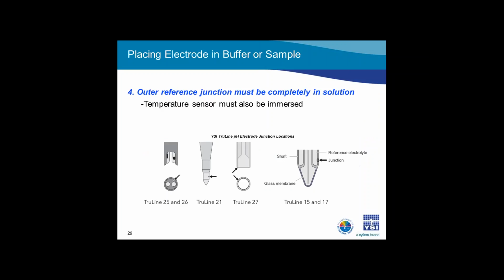Next, as mentioned before, make sure the sensing electrode, reference junction, and the temperature sensor are all immersed in the solution. To accomplish this, it's important to know the physical characteristics of your sensor, like where the reference junction and temperature sensor are located. If you don't know where they are, you can't guarantee they're in solution, so take a moment to get familiar with your sensor. As you can see in this picture, the reference junction location is dependent on the sensor that you're using.